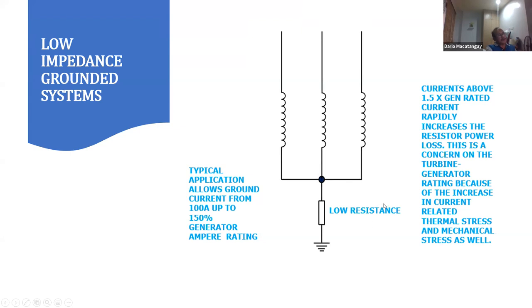But in this type of system, because of the presence of the neutral resistance, when you get to 150% of the rated current, it increases the resistor power loss. This is a concern on the turbine generator rating because of the increase in current-related thermal stress and mechanical stresses as well.